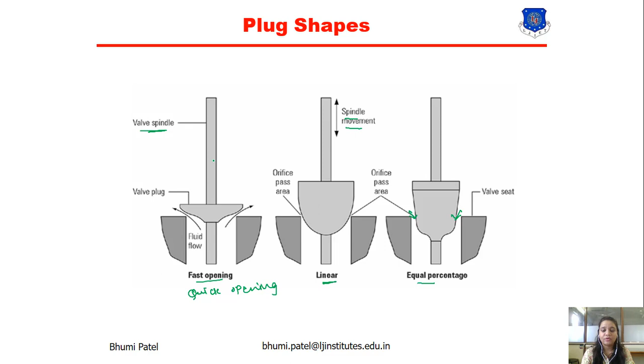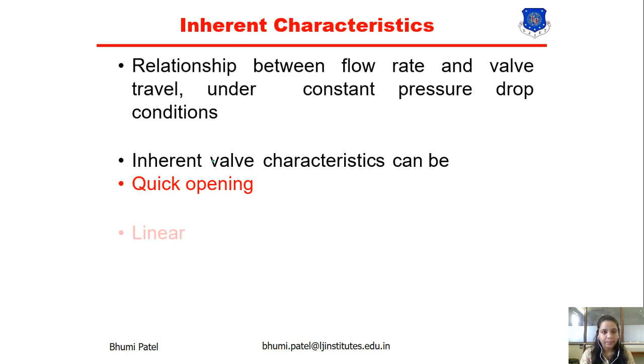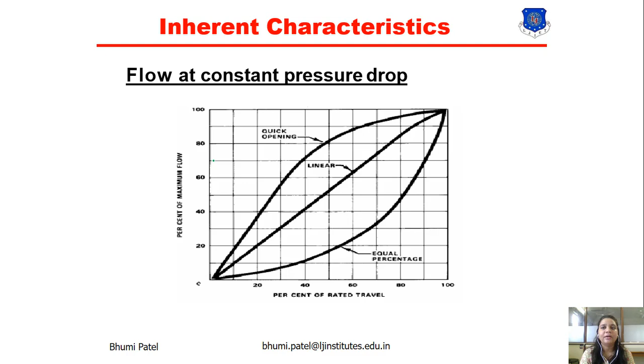Now what is the inherent characteristic? It is the relationship between the flow rate and the valve travel under constant pressure drop condition. Inherent valve characteristic can be quick opening, linear, or equal percentage. So for flow at the constant pressure drop, we can get this type of particular characteristic. It is known as the inherent characteristic. In a general valve, we can get the inherent characteristic.